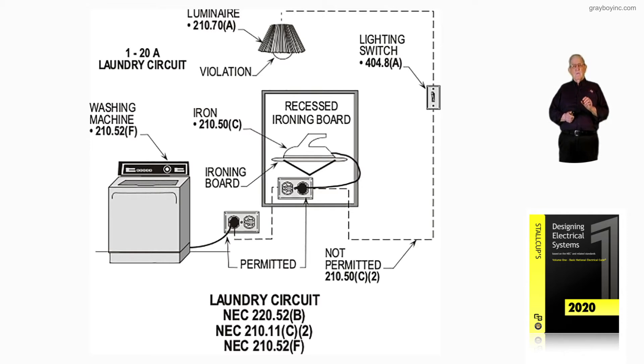We're not going to be covering receptacle locations right now, as we already covered it. Notice the laundry circuit requires one 20-amp circuit, and that one 20-amp circuit is worth 1,500 VA, just as the small appliance circuits are calculated at 1,500 VA.